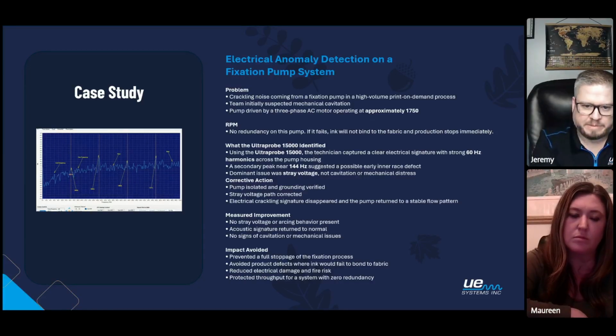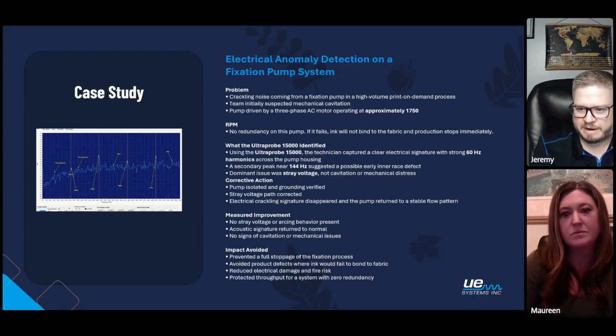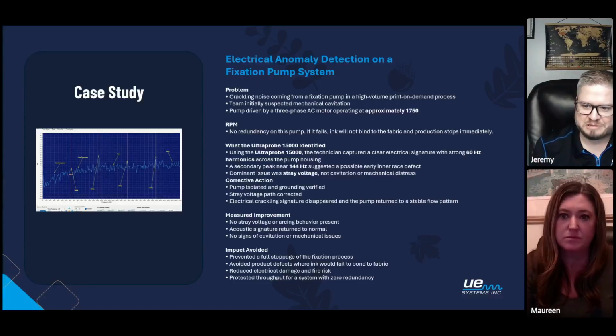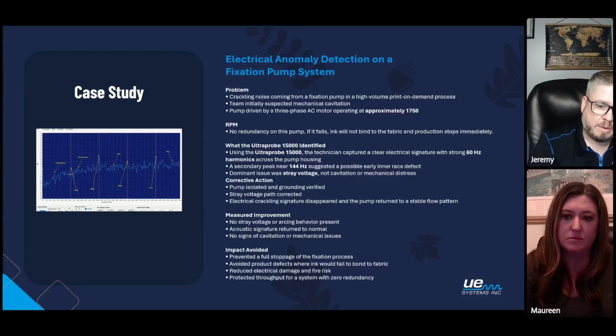So they isolated the pump. They checked the grounding. They corrected the stray voltage that was occurring there. And the crackling actually disappeared right there on the spot. They were standing there with the Ultraprobe and were able to listen to it go away. The pump went right back to its stable flow pattern.